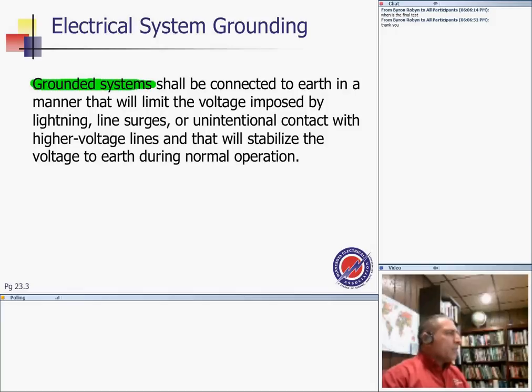Okay, so we're talking about the grounding system shall be connected to Earth. Well, why do we connect them? Look at the reason why we connect it, because of the word limit. A lot of people don't understand that one. Limit the voltage imposed by lightning. You have lightning hitting the transmission line, transferring a huge amount of pulse that goes from here to the load and comes back within milliseconds, and that burns your electronic equipment. To minimize this, we ground the system.